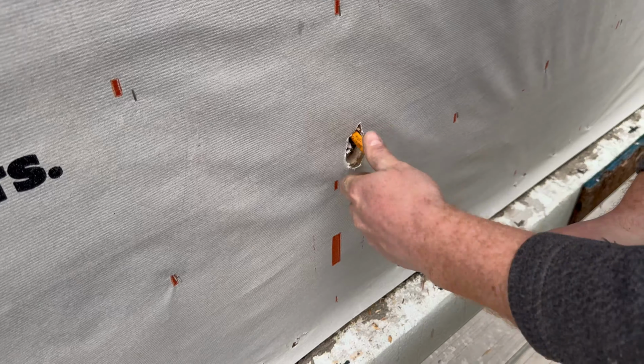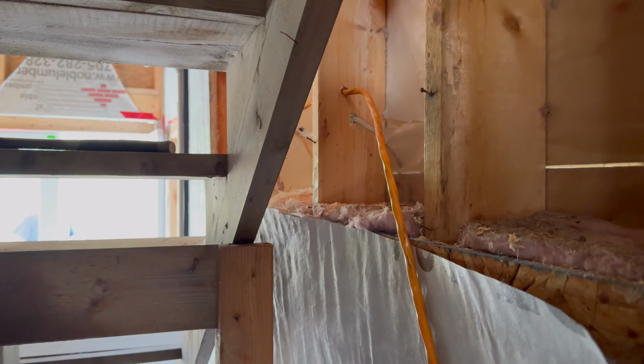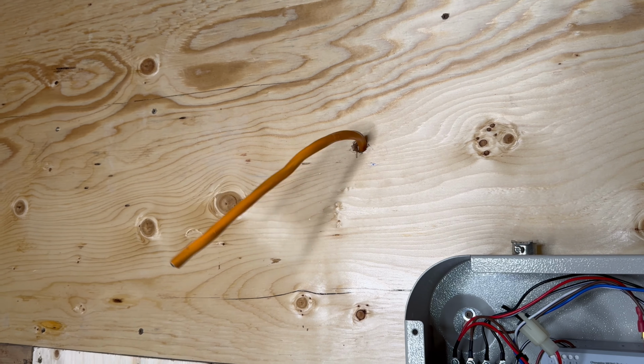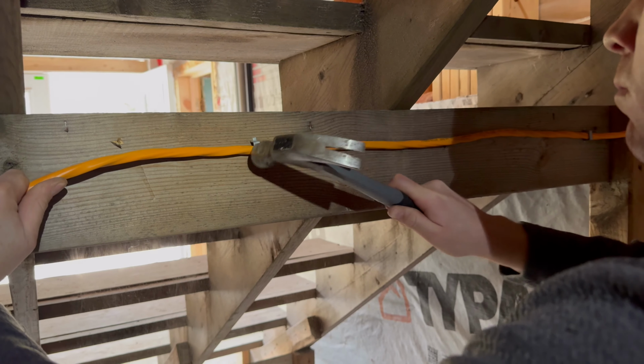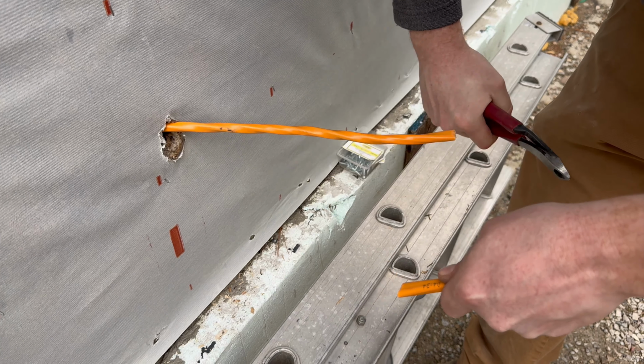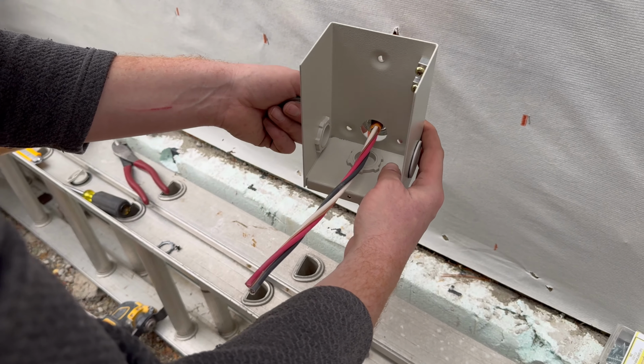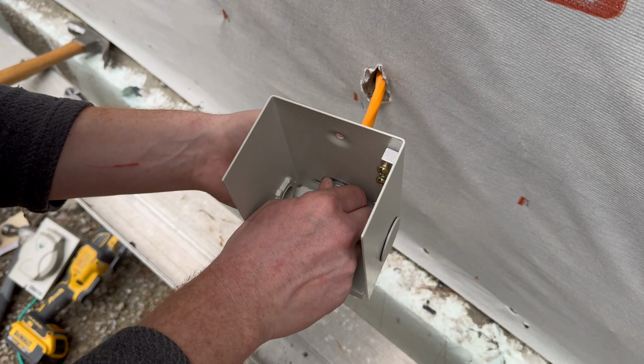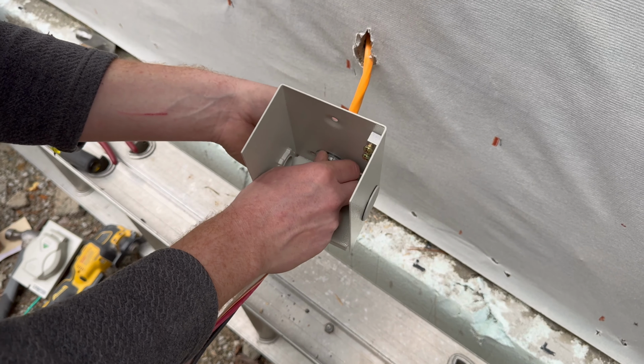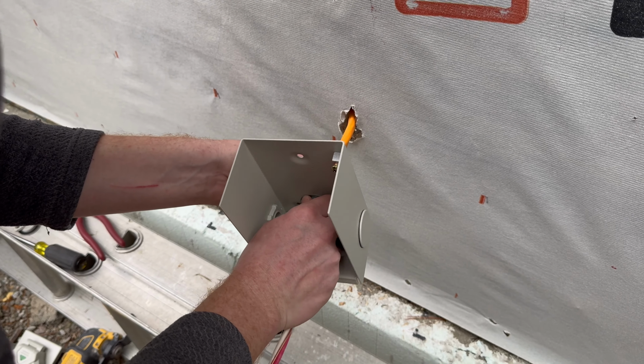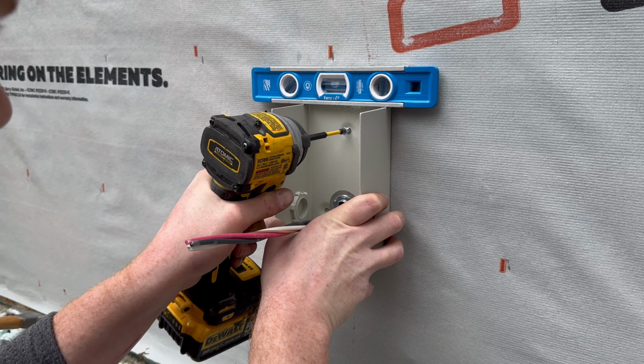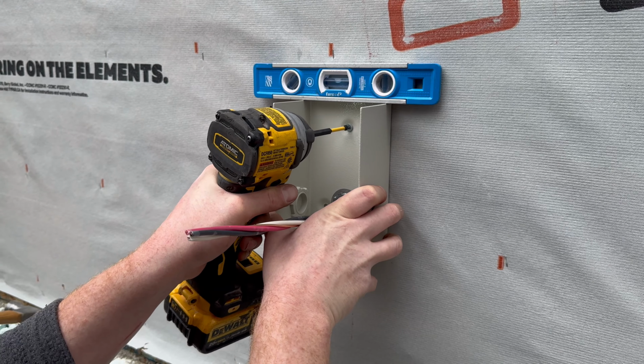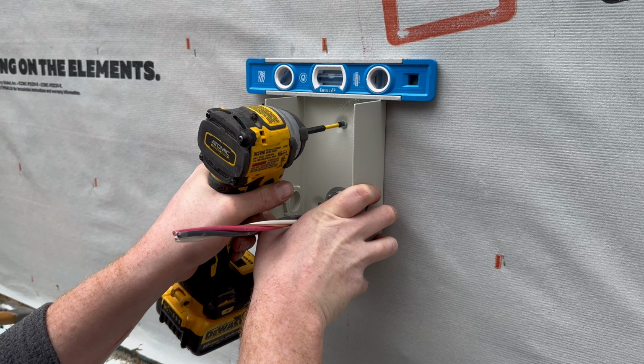Here Mark is running that heavy cable from the outside in through the exterior hole that's been drilled and the holes in the wall studs. Now's the time to install the outlet box with the appropriate cable clamp to secure that heavy cable. Screw it to the wall. Use a small level to make sure you've got it oriented correctly.